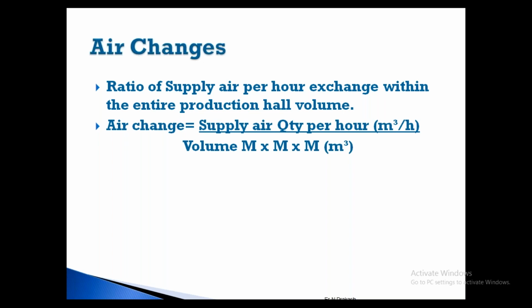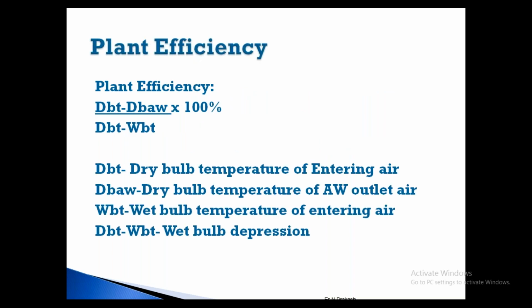Mostly in spinning it will be more, in weaving it will be more. In other departments it will be slightly less, based on the recommendation. This is the supply air quantity and air changes. From the energy point of view, the recommended air changes will be there. We have to see the plant performance as well as the air changes. If you design the plant for a certain air quantity in cubic meters per hour according to the heat load, and it is not performing, and you are asking for more air changes, that means you are supplying more air into the production hall, and so you are using more power to maintain higher air changes.